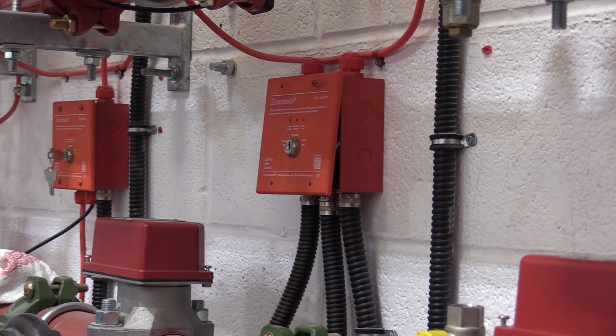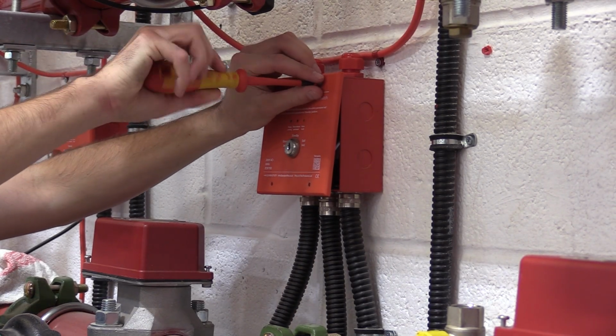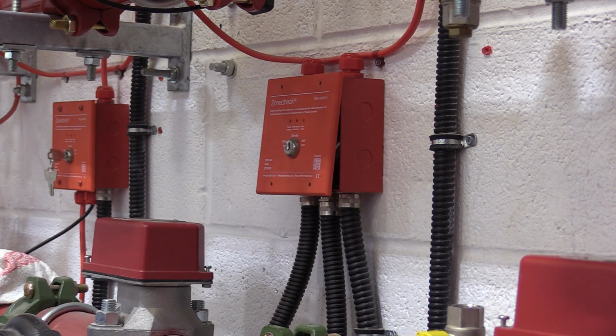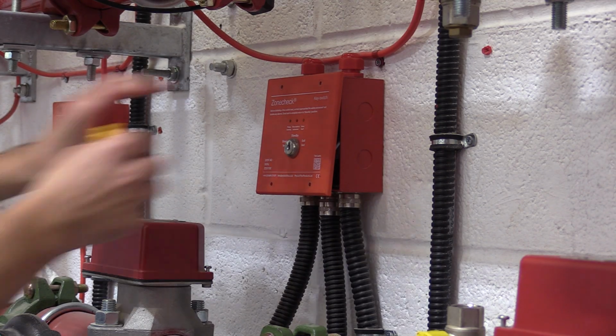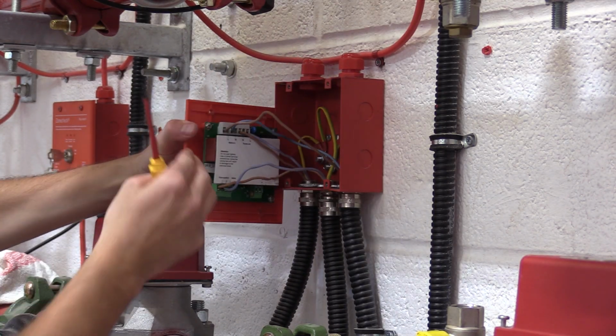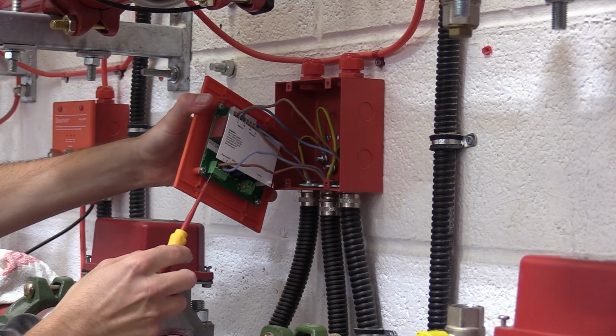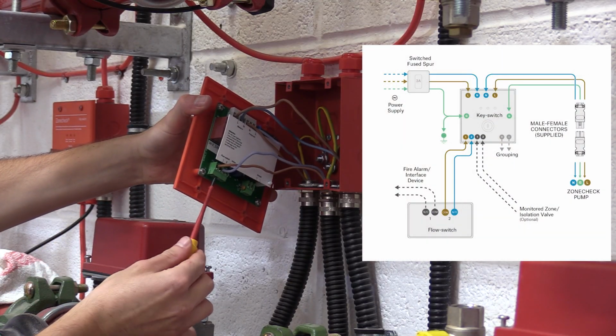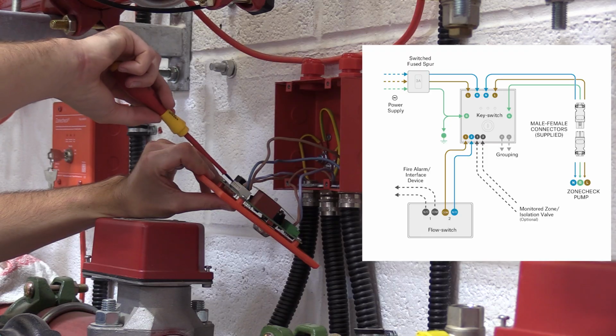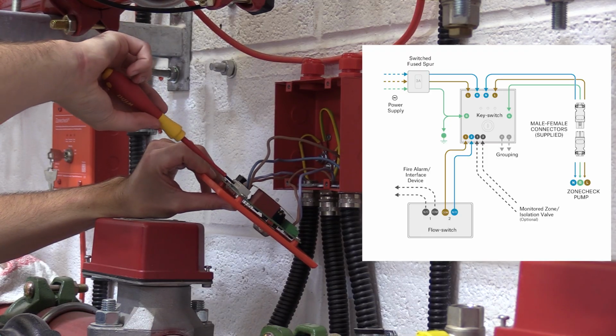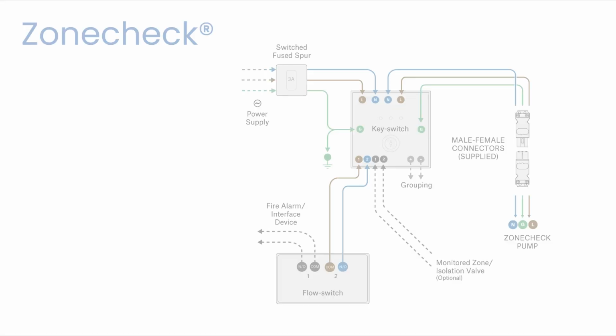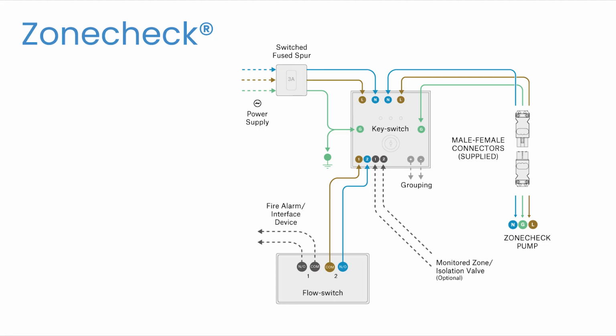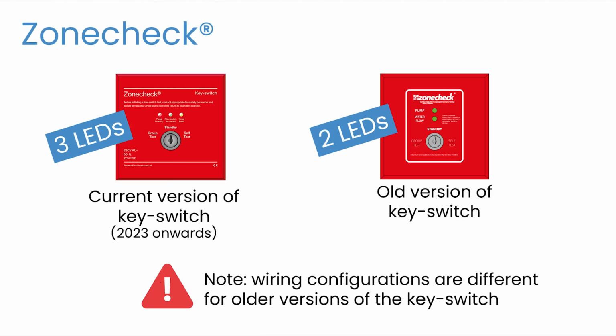Visual electrical inspection. With the key switch electrically isolated, remove the 4 screws around the cover plate. Gently rotate the cover plate so that the wiring can be inspected. Check that all wires are secure and are in the correct position by comparing it to the wiring diagram shown in the instruction manual and repeated here. Please note that older key switches, ones with 2 LED lights on the front rather than 3, have a different wiring configuration. Contact Project Fire if you need assistance with this.